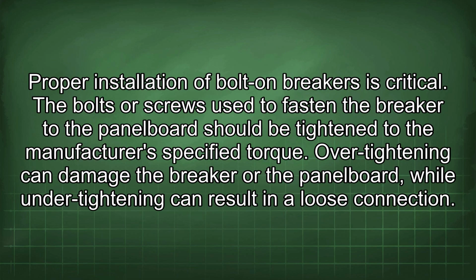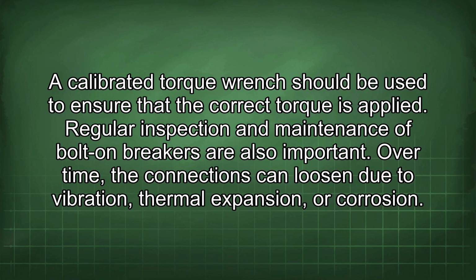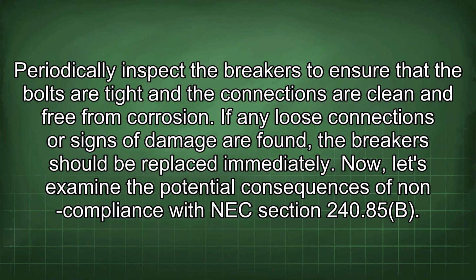Proper installation of bolt-on breakers is critical. The bolts or screws used to fasten the breaker to the panel board should be tightened to the manufacturer's specified torque. Over-tightening can damage the breaker or the panel board, while under-tightening can result in a loose connection. A calibrated torque wrench should be used to ensure that the correct torque is applied. Regular inspection and maintenance of bolt-on breakers are also important. Over time, the connections can loosen due to vibration, thermal expansion, or corrosion. Periodically inspect the breakers to ensure that the bolts are tight and the connections are clean and free from corrosion. If any loose connections or signs of damage are found, the breaker should be replaced immediately.